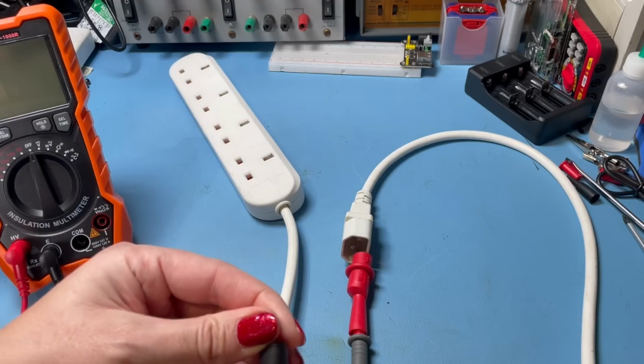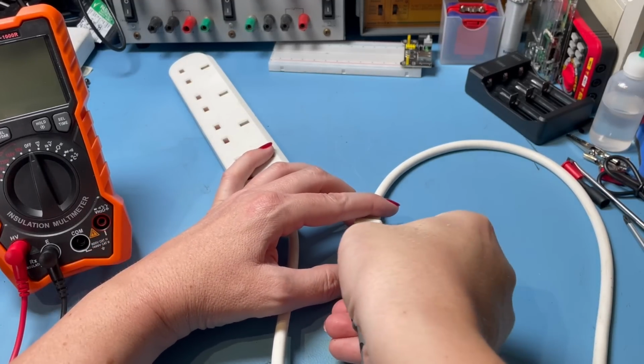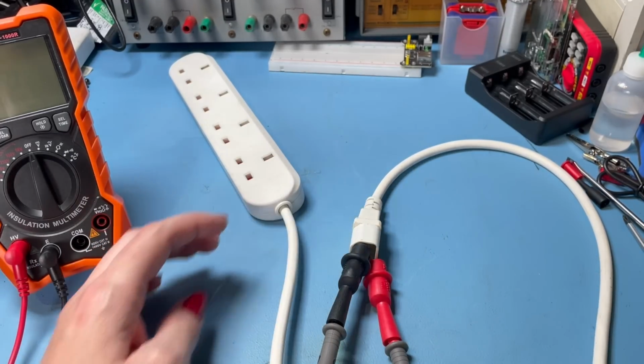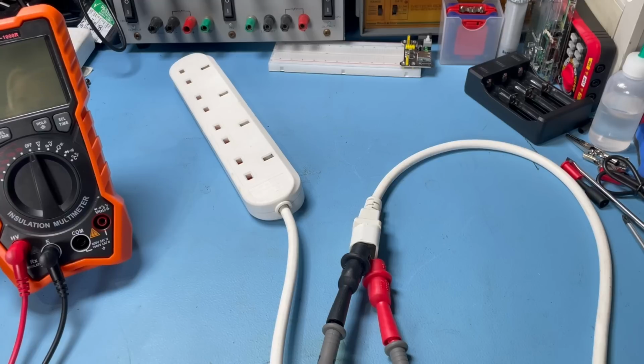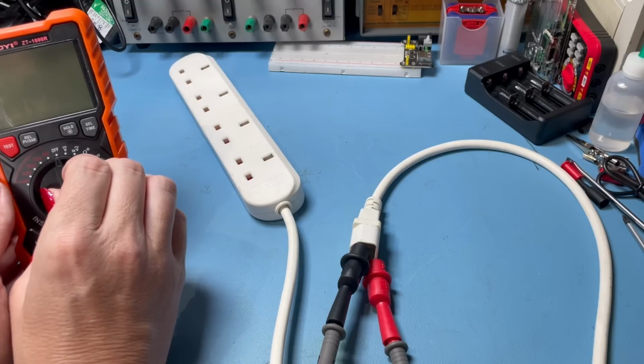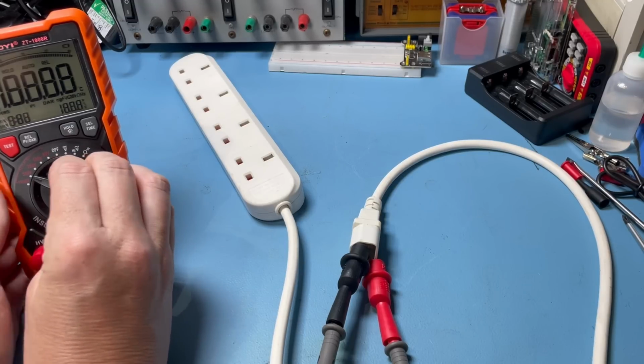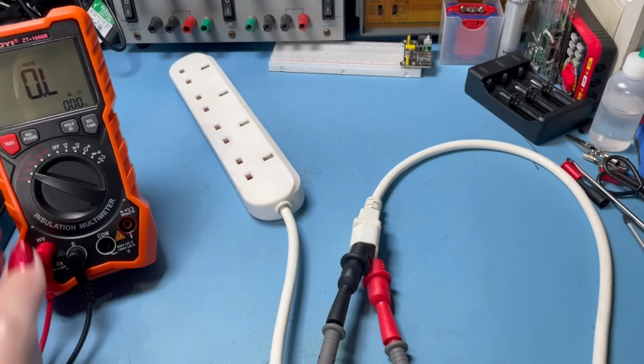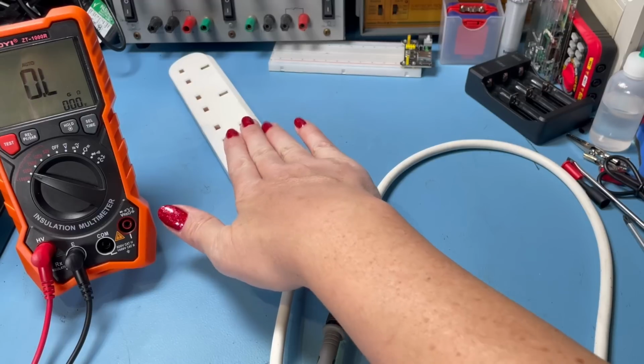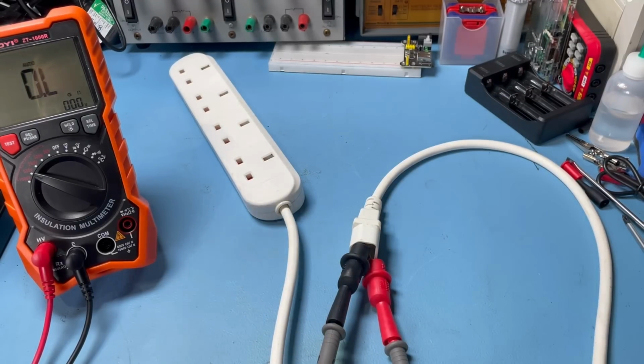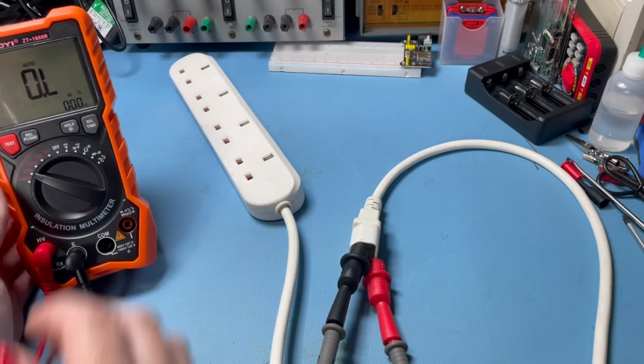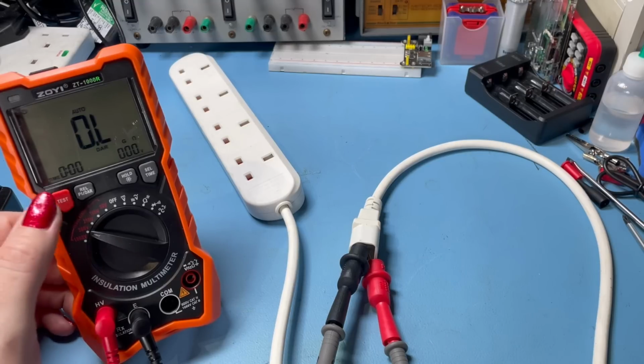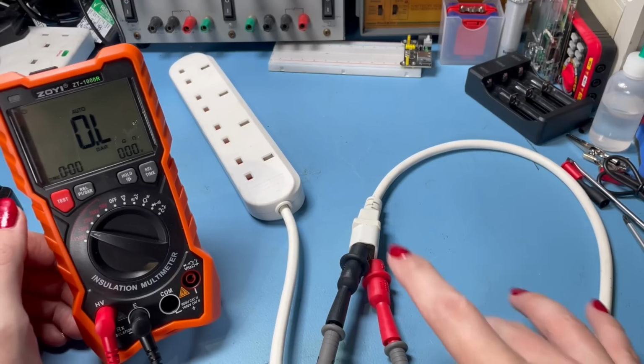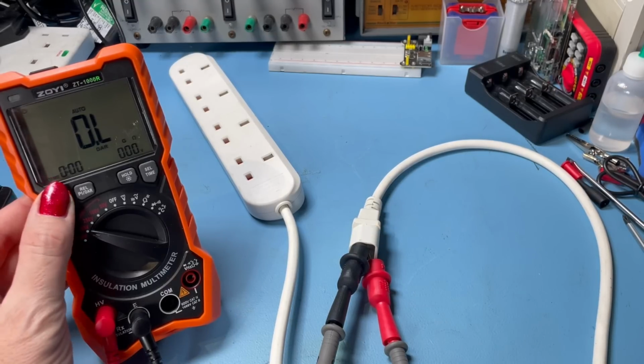It's a good way of checking out your random old extension leads you've got kicking about, or sometimes you buy stuff from eBay. We're going to test some kettle leads in a minute, and we're going to test them up to 1000 volts. We are going to test at 500 volts for this one, because we know this is rated at 250, but we want to be checking it at 500 volts because we want to be really testing the insulation on these things. Okay, so DAR, 500 volts. This is live to earth. Let's test.